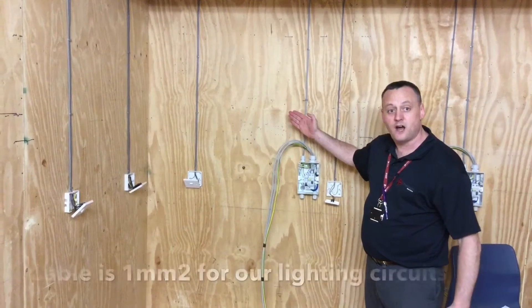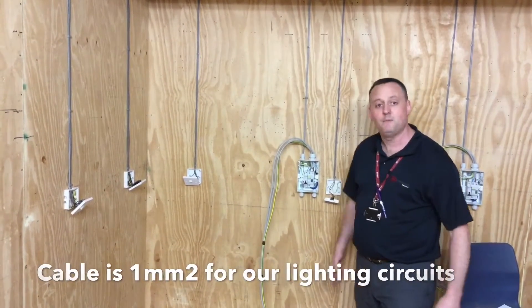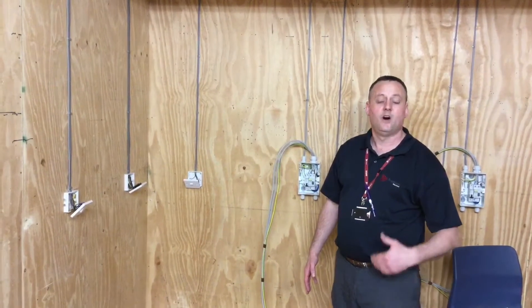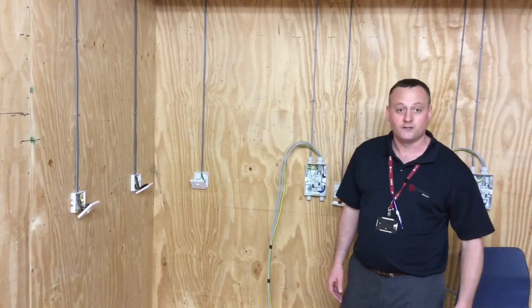At Treshing College, lighting circuits are installed using 1mm² PVC twin CPC cables. On site, that cable size will often be 1.5mm² for reasons of insulation in roof spaces and higher ambient temperatures in roof spaces in domestic properties. So we will use 1mm here, 1.5mm on site.